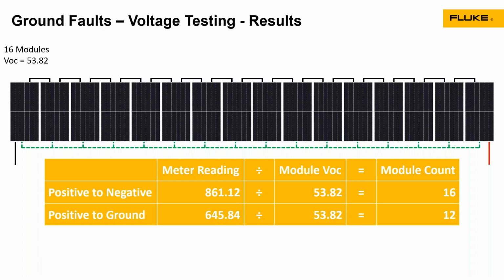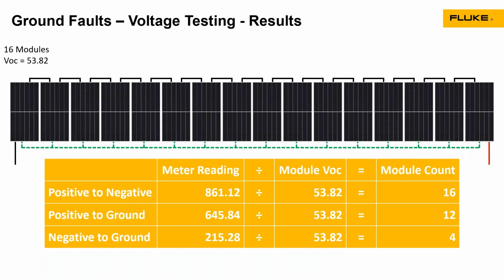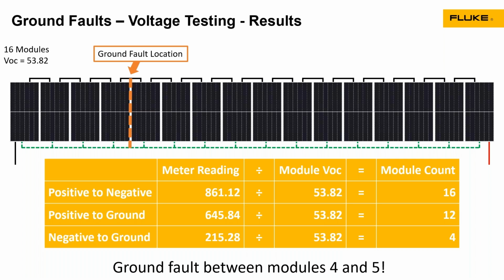When I measure my 645 volts positive to ground and divide by 53, I get approximately 12 modules. When I divide the 215 by 53, I get approximately 4 modules. What this tells me is that there's a ground fault 12 modules from the positive to where the ground fault is, and 4 modules from where the negative is to the ground fault. So if I'm counting from my negative side, this means the ground fault is between module 4 and module 5 of the string. With that information, I can get the string layout. I can go out into the array, figure out where these modules are, and try to do a visual inspection to see where the problem is, and then repair that ground fault.